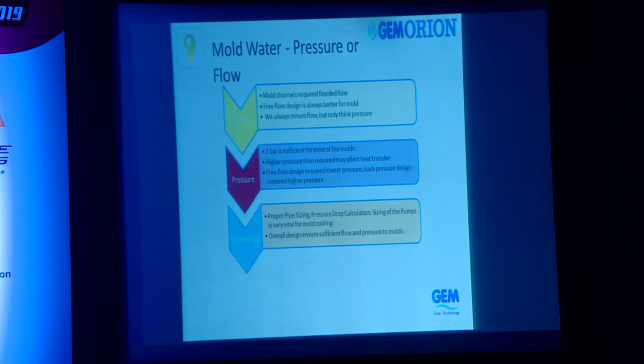So we always think about pressure. Actually, if you see, for the water to just free flow through and return on gravity or mild pressure to a tank, only 2 bar is sufficient. But we see a lot of mold requirements where people go for 4 bar, 5 bar, 7 bar, 8 bar, so this may not be required.